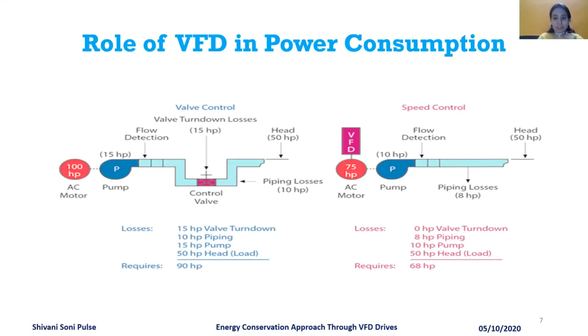Basically in fan and pump applications, the flow or the volume varies linearly with the speed. There are two or three statements for the affinity laws. If the flow is increased, speed is also increased. If the speed is decreased, your flow will be decreased. In the same way, if the pressure or the head pressure varies, it is directly proportional to the square of the speed.